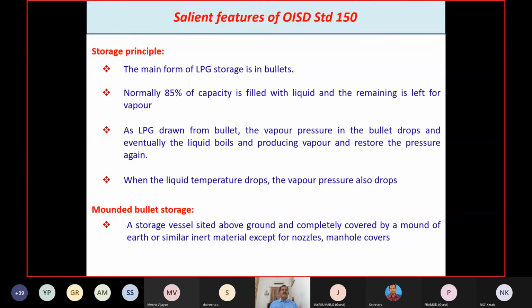As LPG is drawn from the bullet, the vapor pressure in the bullet drops and eventually the liquid boils, producing vapor and restoring the pressure again. So when the liquid temperature drops, the vapor pressure also drops. Now, mounded bullet storage: a storage vessel sited above ground and completely covered by a mound of earth or similar inert material, except for nozzles and manhole covers.